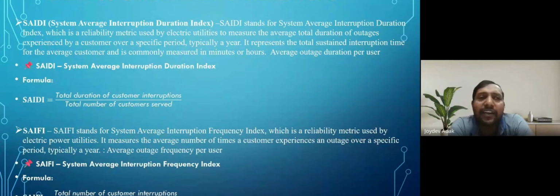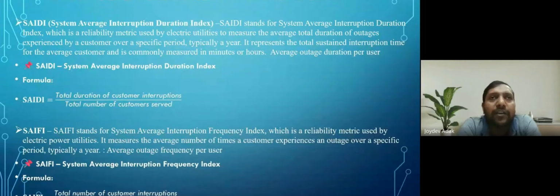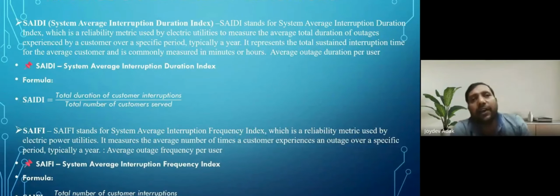And SAIFI is the system average interruption frequency index. How many times interruption occurs per consumer on an average basis. This is the SAIFI. As a mathematical formula, it is the total number of customer interruptions. Suppose customer 1 has 5 interruptions, customer 2 has 1 interruption, and customer 3 has 3 interruptions. The total interruption is 5 plus 1 plus 3 plus so on. That is the total number of interruptions. And total consumers is 30. So the value we obtain by dividing by the number of consumers is the SAIFI.